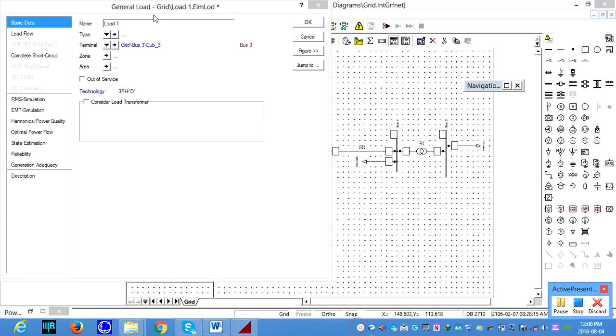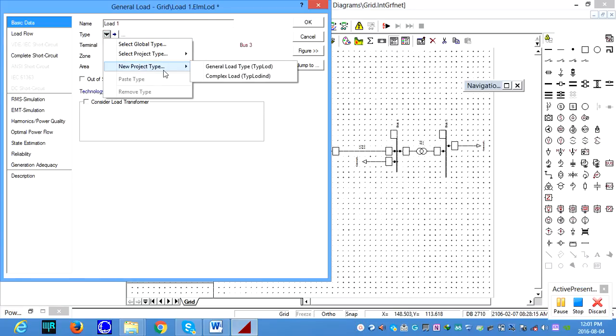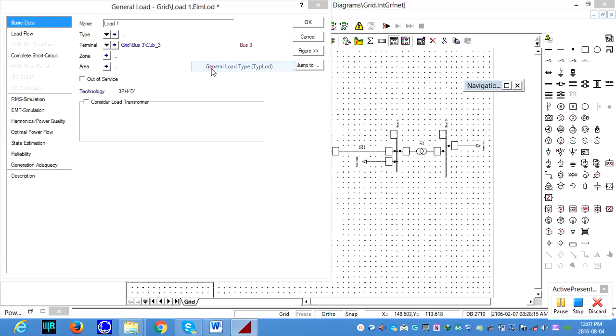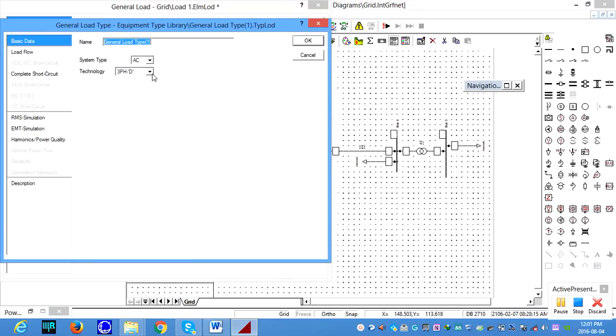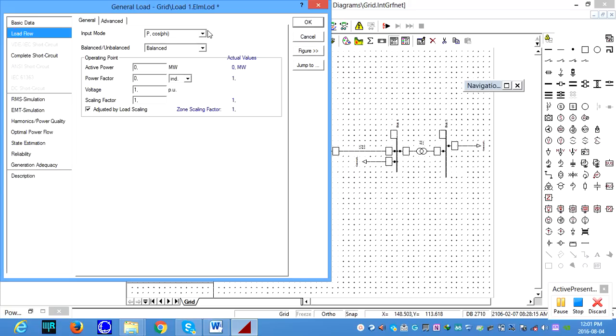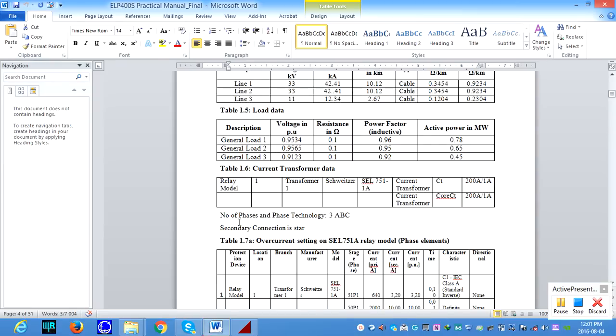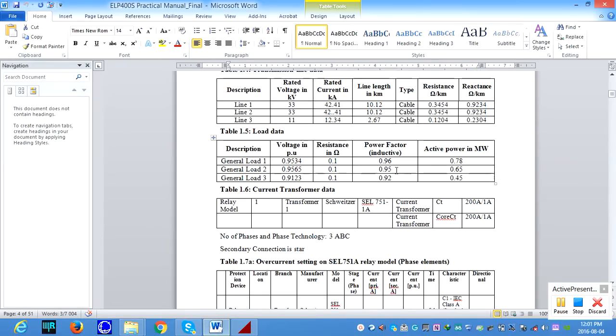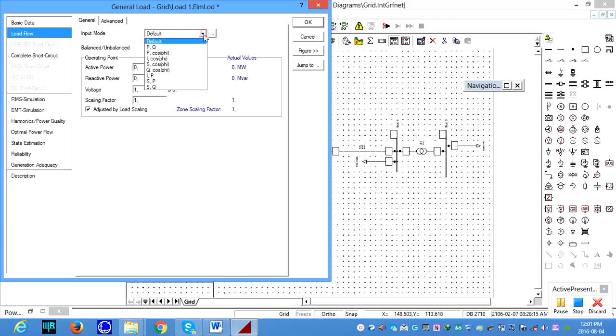Okay, for the load, we can go to the type, select a new project and general load type. Okay, make sure this is, there are different types of technology, three phase delta, three-phase with earth, or three-phase Y-connected with neutral, and different types of load. In this case, we use three-phase delta. Okay. Next, we go to the load flow data. There are different types available. Default looks like this, but we can change the input mode according to the data. But let me look quickly at our data table. We have active power and power factors, so we need to set the type of load as active power and power factor, that is P and cos phi.